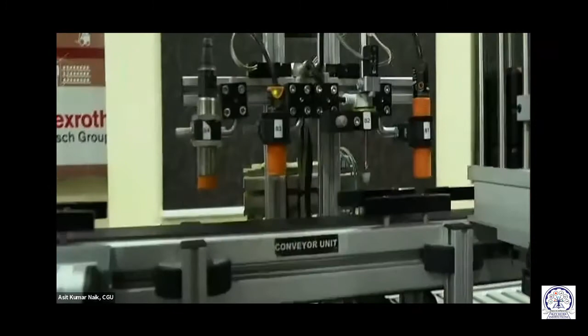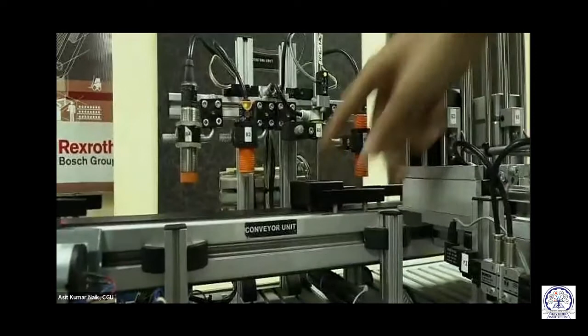In case a metallic object has come in this manner, you can see that though it extends, this reed switch is never reached. This will give us feedback that the metal object was not in the correct orientation. Similarly for the black object, this is the favorable condition. That means the flat side should be facing upwards. In case a black object, or this plastic workpiece, is in this orientation, wherein this cylinder can fully extend, we will be able to conclude that it has come in a wrong orientation for the process. Hence we can take the necessary steps.